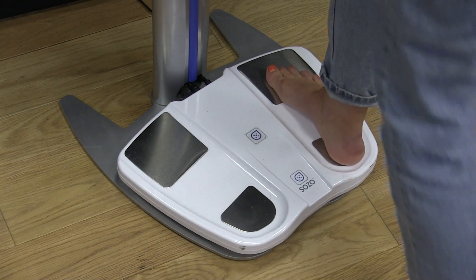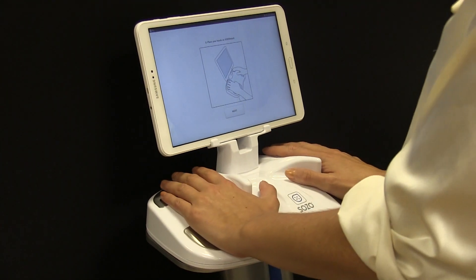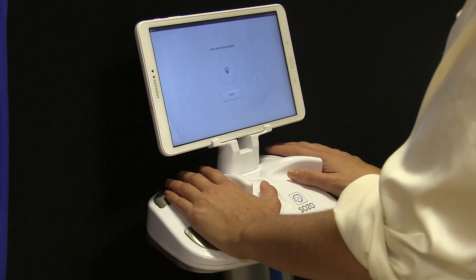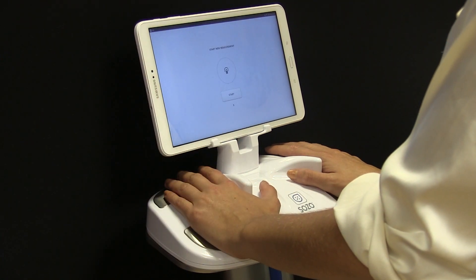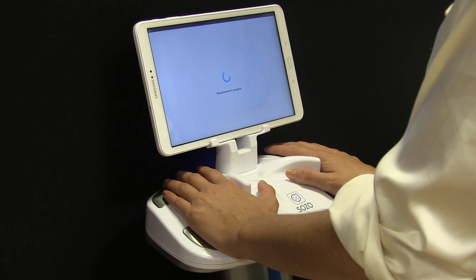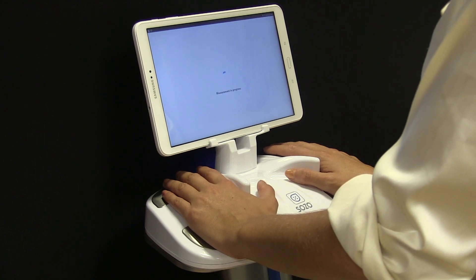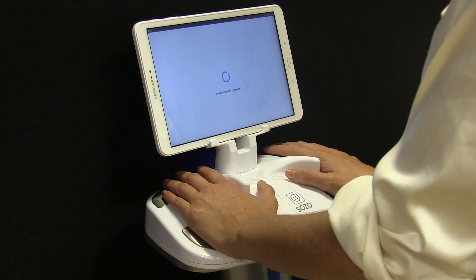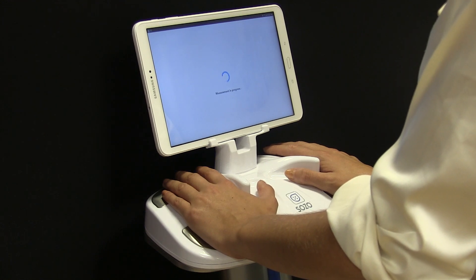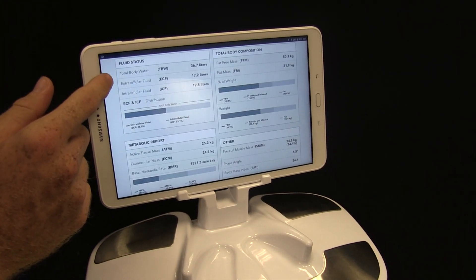By using 256 frequencies from 3 kilohertz to a thousand, Sozo Pro measures the reactance and resistance of the body tissue to calculate fat mass, fat free mass, extracellular fluid, intracellular fluid and total body water, which is specific to the individual. This is unlike manual techniques which are subject to human error, and bioimpedance analysis which uses 1 to 11 frequencies and compares to population data.